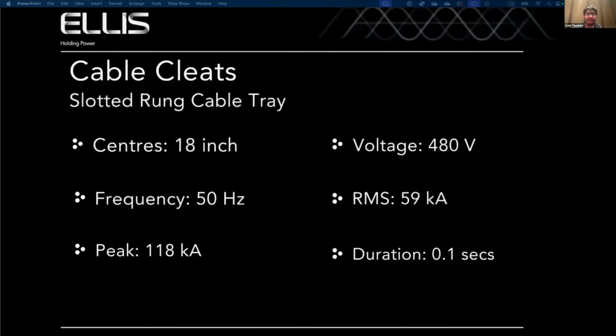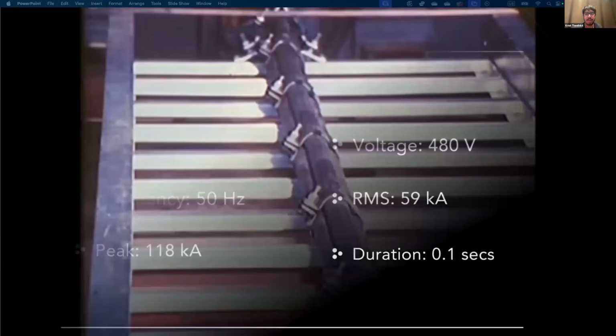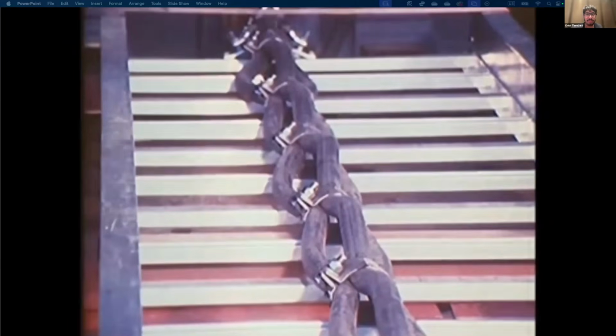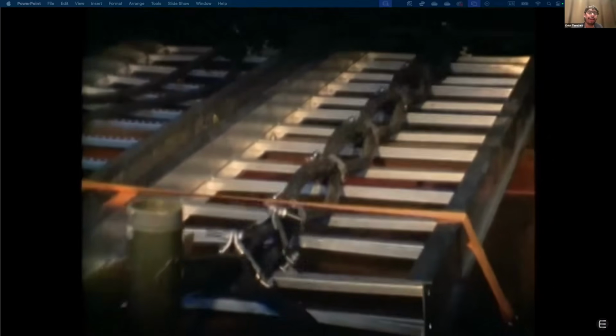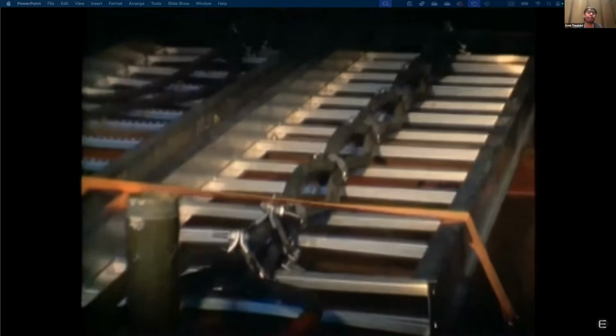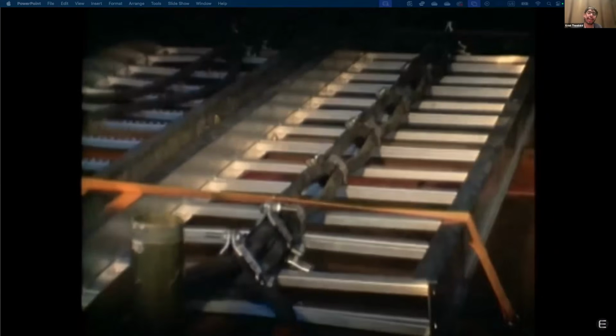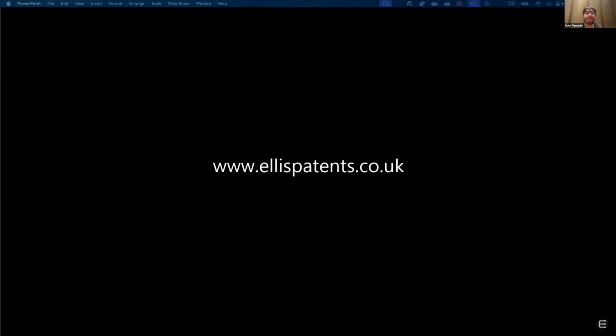Can see again. This is without any cable cleats, because the cleats are supposed to withstand that short circuit current for a certain amount of time. But with the cleat, they are able to correctly withstand everything and stay in place. So it's very, very, very important.